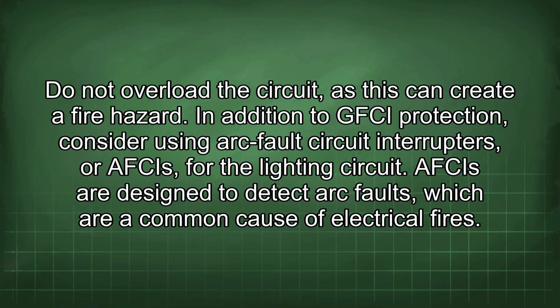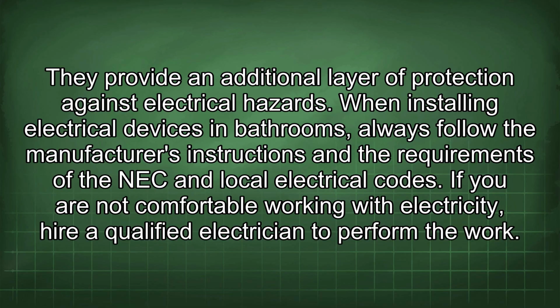In addition to GFCI protection, consider using arc fault circuit interrupters, or AFCIs, for the lighting circuit. AFCIs are designed to detect arc faults, which are a common cause of electrical fires. They provide an additional layer of protection against electrical hazards.